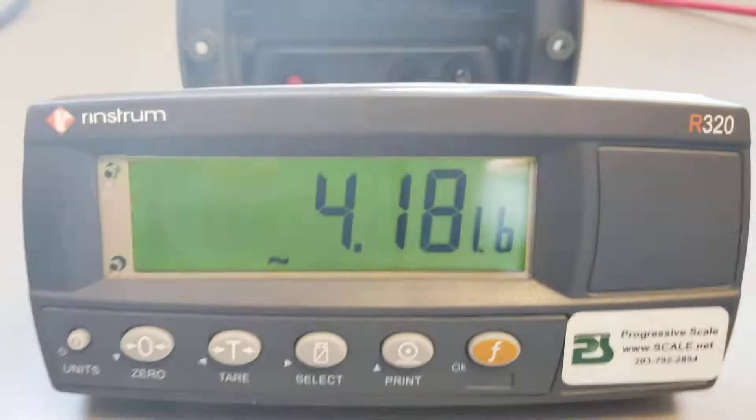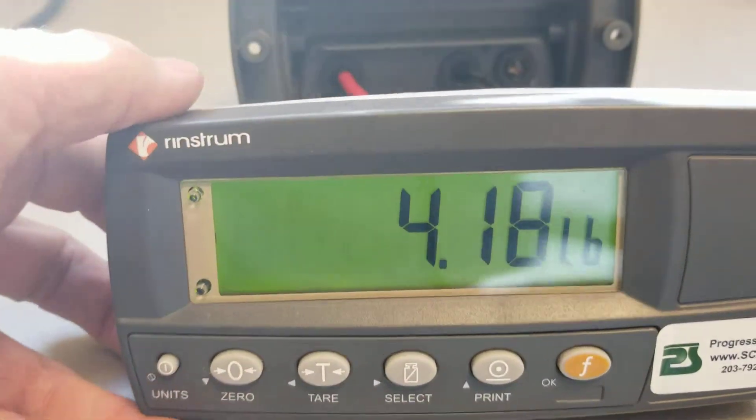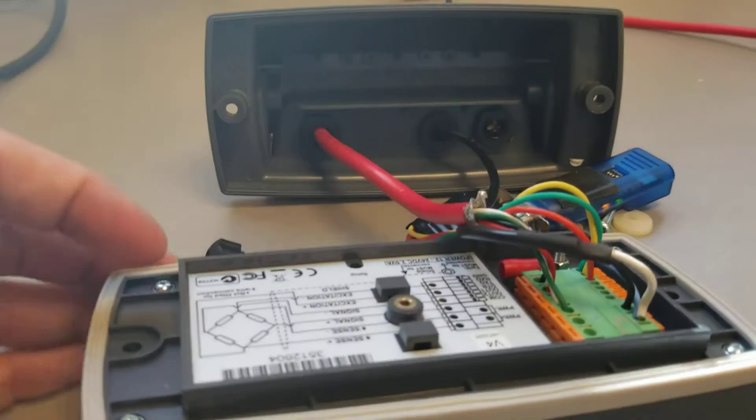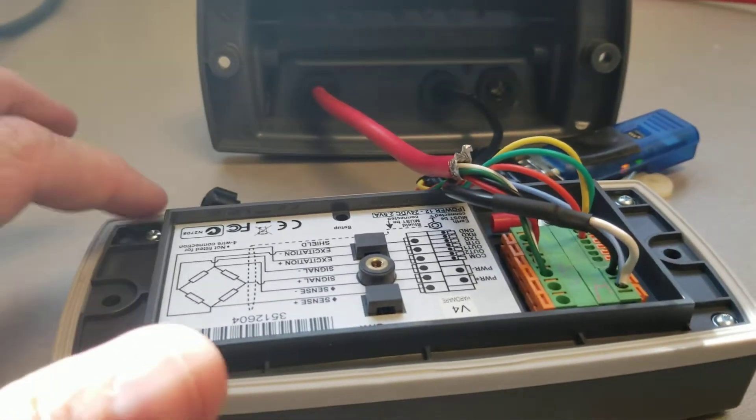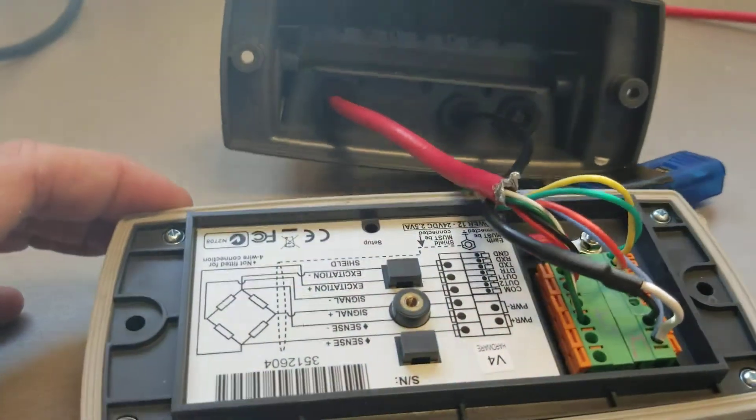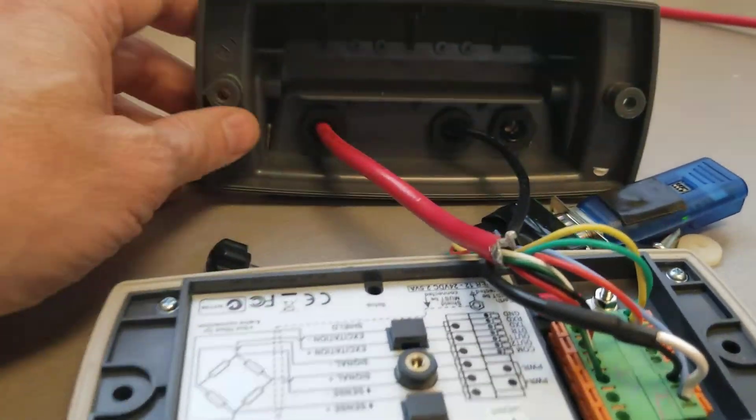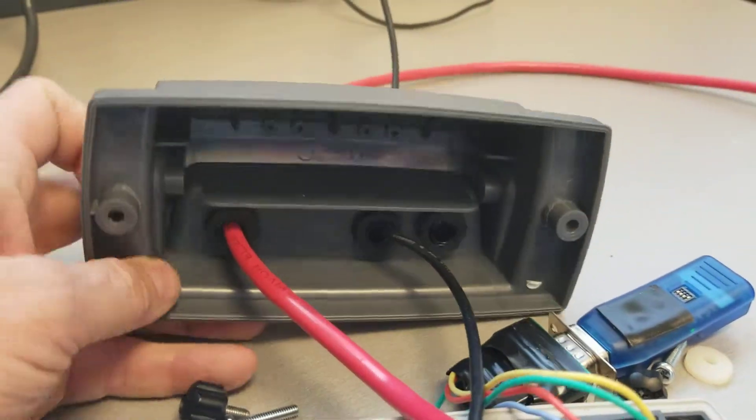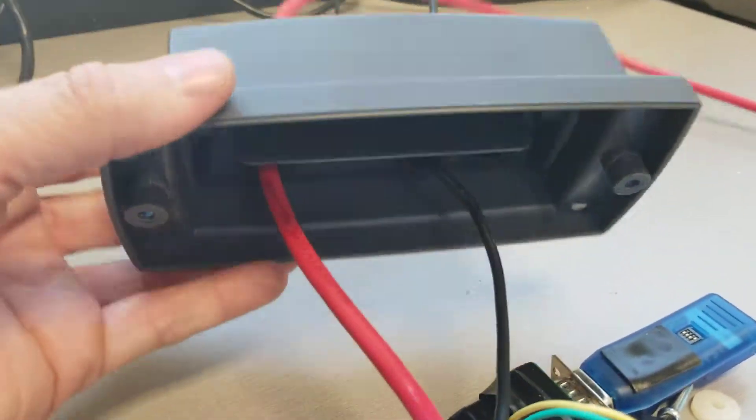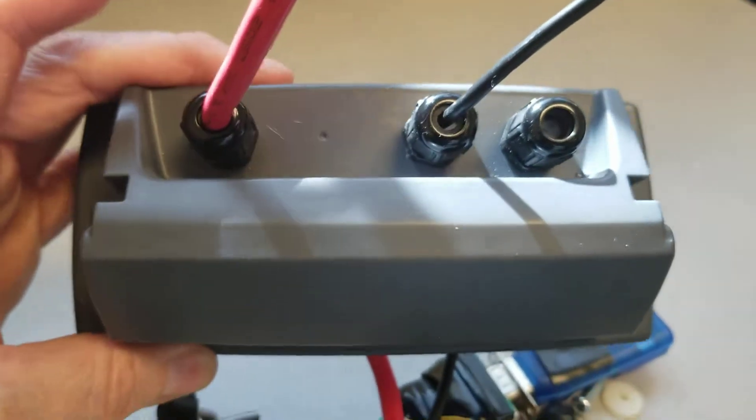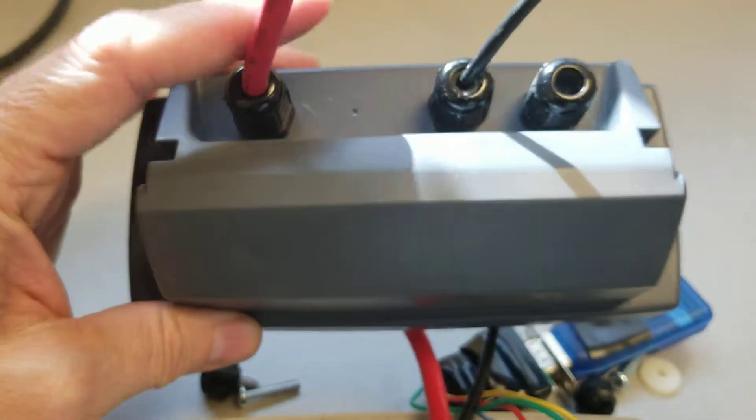This indicator I'm going to show you the back now. It can be panel mounted on that thing. You can see here you've got gasketing around it so if you were to panel mount it, it would be sealed. Same thing with this back. This back comes with, if you were to get the back on it, you put strain reliefs on it.